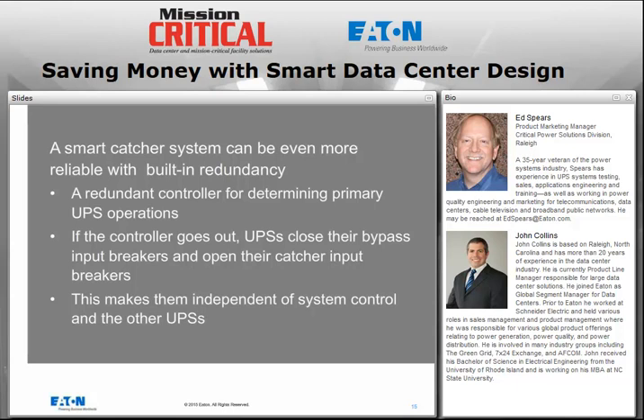If the entire control system, literally Elvis leaves the building, all the UPSs will automatically close their traditional bypass breakers, so they'll be fed with bypass power, and that will again happen automatically and will happen in the absence of any kind of control whatsoever. So this makes the UPS systems independent of any system control and any master system brain, which is strongly desired in the systems that we make. We don't want to depend on a single brain for anything in a highly redundant system like we're describing here.